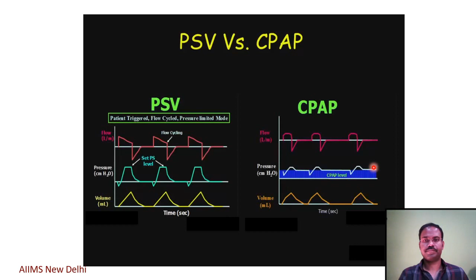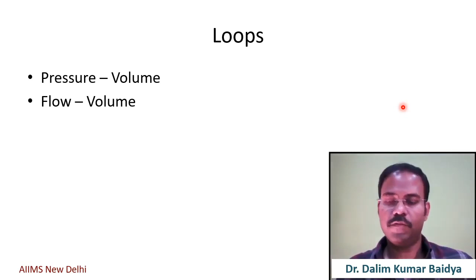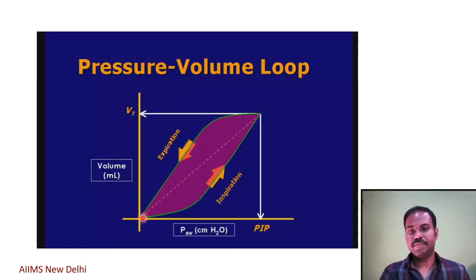Now let us examine closely and interpret the variety of loops. We have two different types of loops: pressure volume loop and flow volume loop. The first figure shows the pressure volume loop. Here the pressure is on the x-axis and volume is on the y-axis. This is a typical picture of the pressure volume loop of VCV mode. Inspiration begins, and there is a rise in the inspiratory pressure till it reaches the peak inspiratory pressure, and the set tidal volume is delivered, and then expiration starts when the volume comes out and pressure gradually comes down and reaches the baseline.